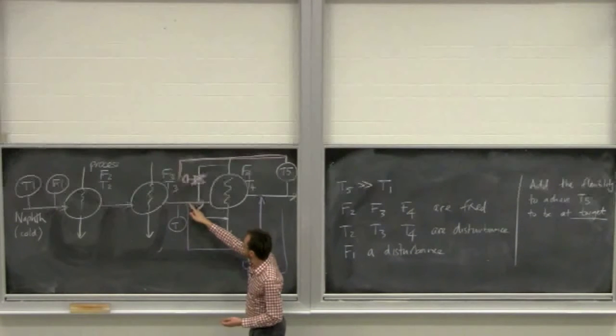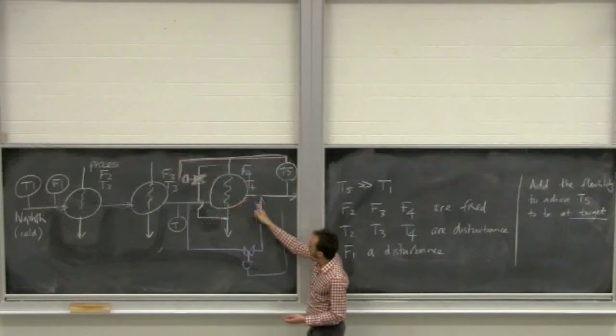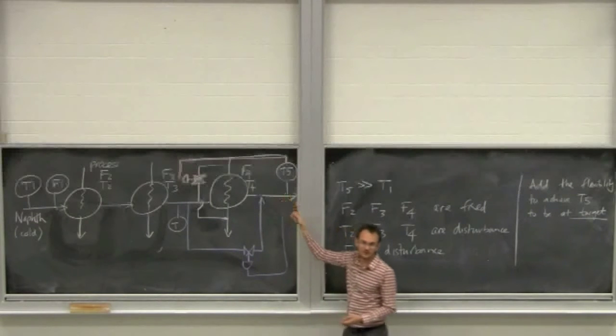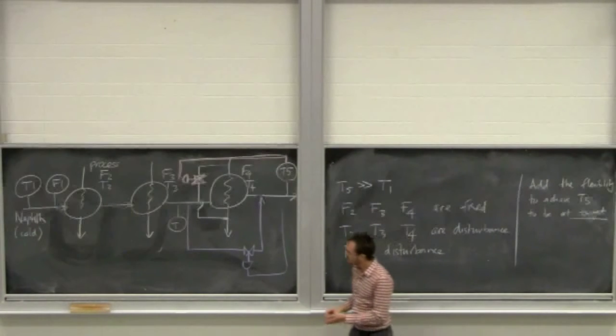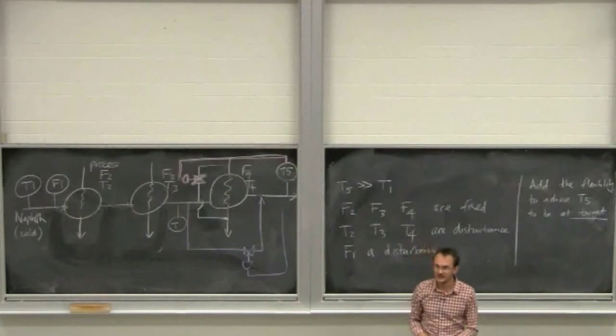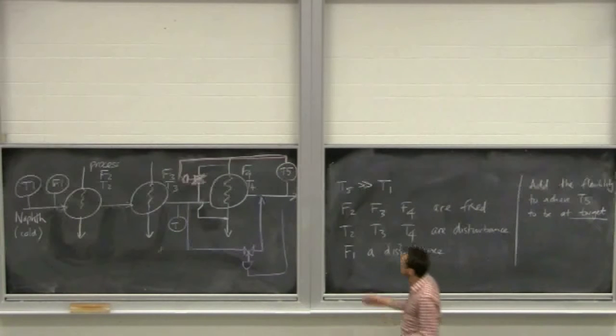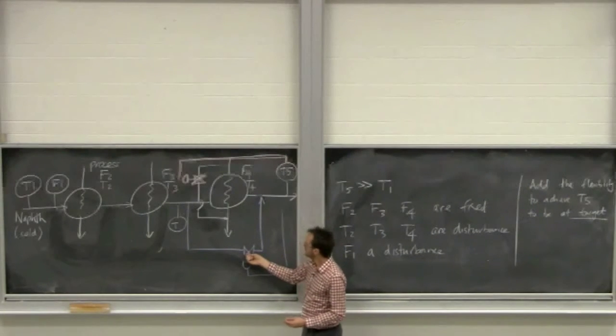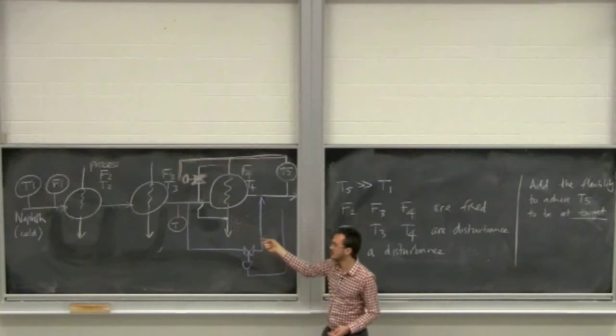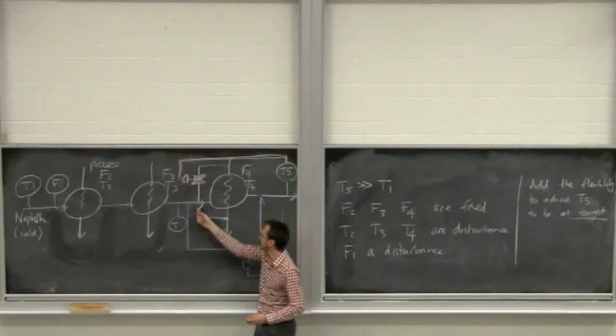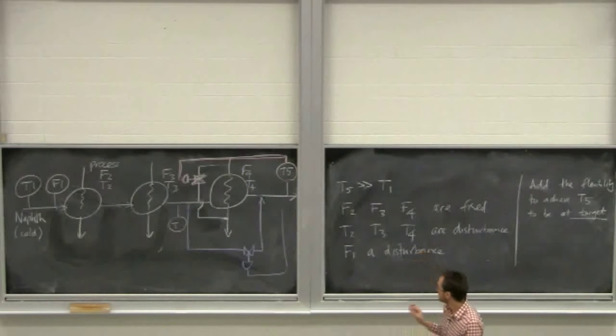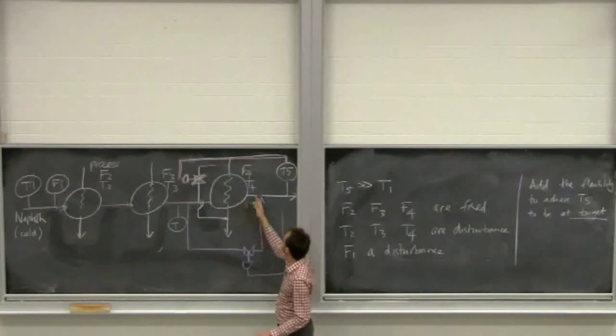let's just discuss quickly purple and red. The purple option here essentially says that at this point we've got enough heat that's still colder than T5 and if we go straight through the heat exchanger, so no bypass, we're going to probably overshoot that temperature at T5. And so, what the bypass does is we open and close it to meet target. Okay.